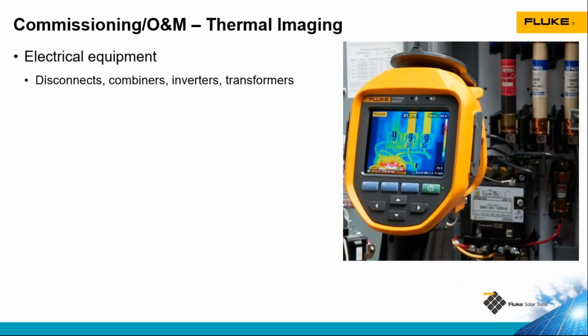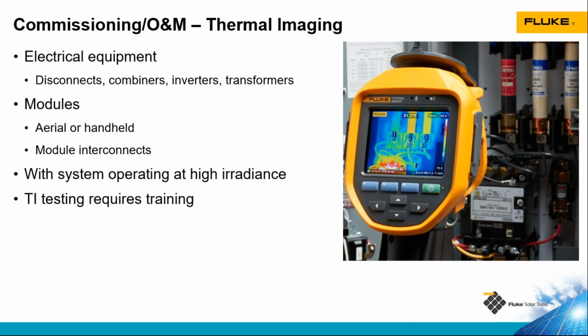And during commissioning and in operations and maintenance, we can use thermal imaging to identify problems with the system. We can use handheld thermography to look at any of our electrical equipment like disconnects, combiner boxes, inverters, our medium voltage transformers. We can also use thermography on our modules, both handheld thermography for spot checking and more frequently used aerial thermography, where we have a drone with a thermal camera, flies over the array, taking pictures. We're going to take those pictures, put them into a software. The software will process the images and tell us where there are issues that need further troubleshooting.